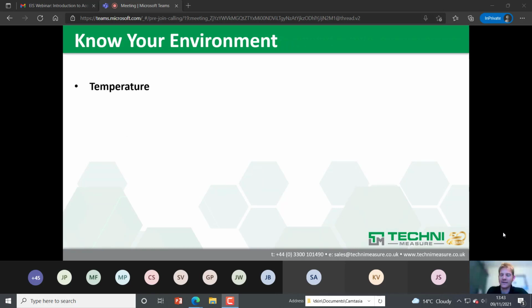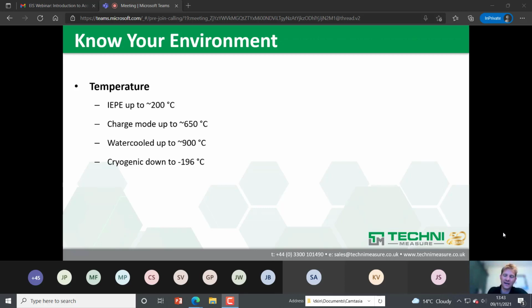Okay, so that's your actual measurement, some of the key parameters. Knowing your environment is the next one. So where are you going to put your accelerometer? Temperature is perhaps one of the most important factors to look at. As Keith mentioned, some IEPE electronics can just about get to 200 degrees C, but generally you're down at 120, 160 or 180 degrees C with the IEPE inbuilt electronics. Charge mode, you can get up to around 650 degrees C.